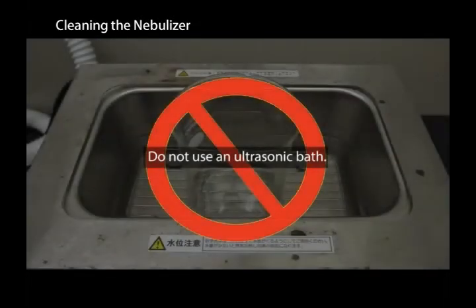Using ultrasonic cleaning can damage nebulizers. Do not clean nebulizers in an ultrasonic bath.